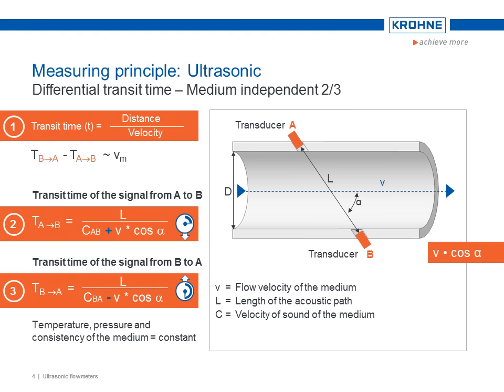In practice, we can assume that since neither the temperature, nor the pressure, nor the composition of the medium will change in these intervals, that is, within milliseconds, they remain constant. So, during the transit time period, the velocity of sound can also be seen as constant.